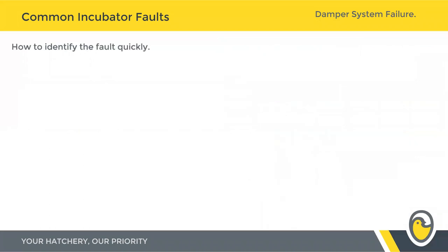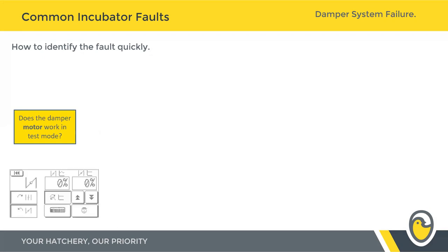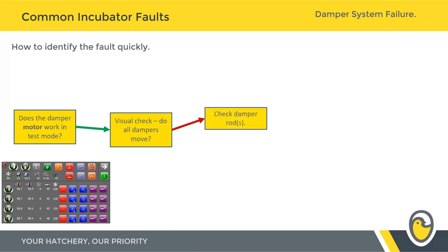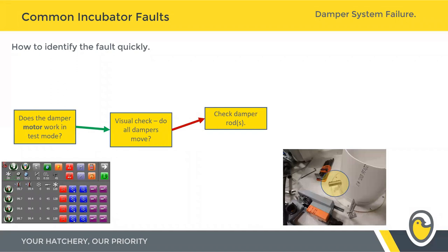Now we're aware of a fault with the damper system and we need to identify it as quickly as possible — ideally without going inside the machine, but being aware we may need to transfer the eggs to give ourselves time to work in a more relaxed manner. Go into test mode straight away and manually drive the damper open and closed. Does the damper motor physically move? On a Gen 4 monochrome, Gen 4 colour, or Rock screen, you've got all the functions there to drive the damper open and closed.